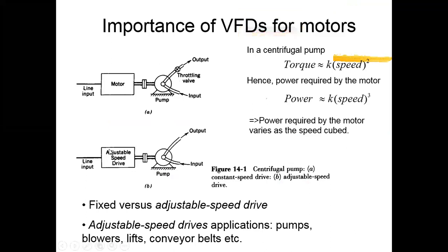So variable speed drive means these are outdated, 20 years old outdated things. Let's say you want to control the flow. You have a motor, you have a pump, you have a throttle valve. You open and close the throttle valve to control the flow. Then what happens is the pump pushes the water. This water is hitting the valve.